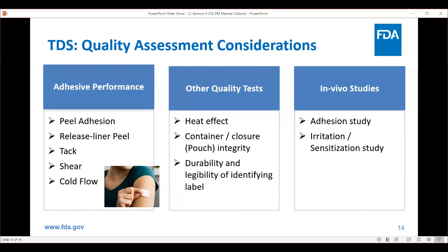I'm referring here to critical in vivo studies for TDS, which are adhesion study and irritation sensitization study. It's recommended that the specification acceptance criteria or specification limits for all these adhesive performance tests mentioned in the slide shall be for the commercial batches established based on the submission batches which are used in these two in vivo studies. For more comprehensive list of the test and data required, you can always refer to the TDS product quality guidance, which was published in November.